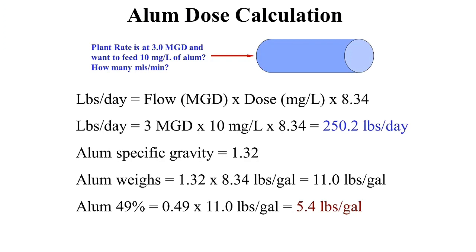Now we need to convert the 250 pounds per day to our specific chemical, which is 49% alum. We multiply the specific gravity of alum, which is 1.32, times 8.34 — the weight of one gallon of water — and determine that a gallon of alum weighs 11 pounds. But only 49% of alum is aluminum sulfate.